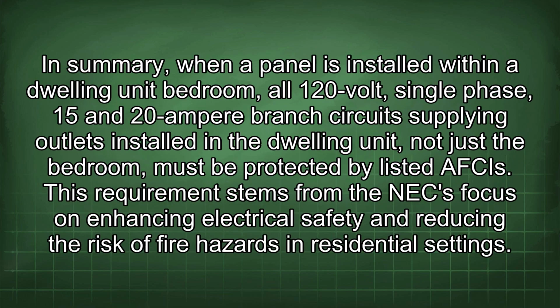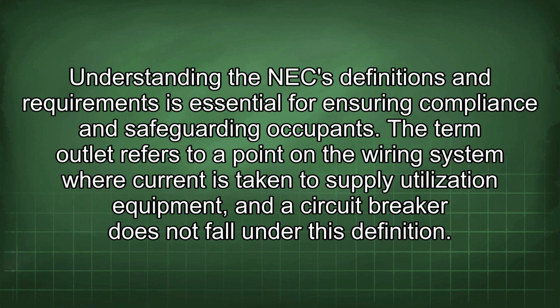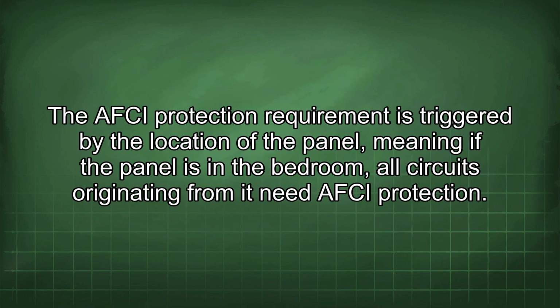In summary, when a panel is installed within a dwelling unit bedroom, all 120-volt single-phase 15 and 20 ampere branch circuits supplying outlets installed in the dwelling unit, not just the bedroom, must be protected by a listed AFCI. This requirement stems from the NEC focus on enhancing electrical safety and reducing the risk of fire hazards in residential settings. Understanding the NEC definitions and requirements is essential for ensuring compliance and safeguarding occupants. The term outlet refers to a point on the wiring system where current is taken to supply utilization equipment, and a circuit breaker does not fall under this definition. The AFCI protection requirement is triggered by the location of the panel, meaning if the panel is in the bedroom, all circuits originating from it need AFCI protection.